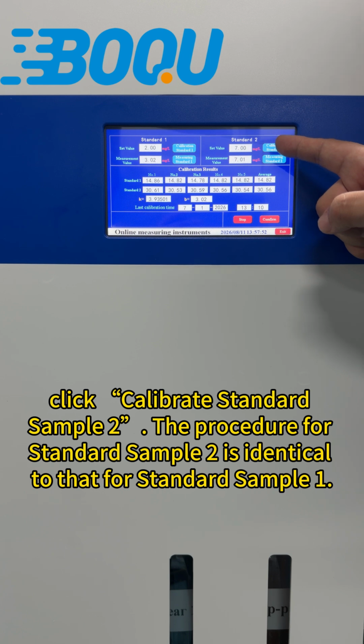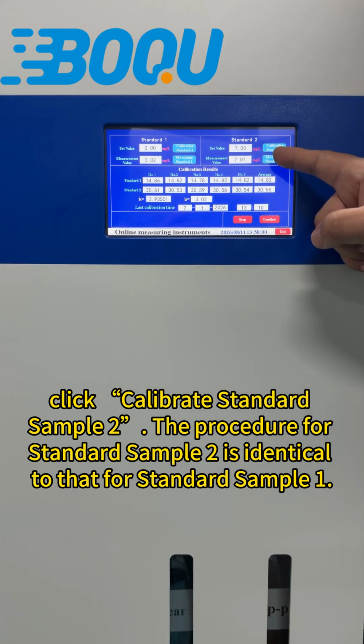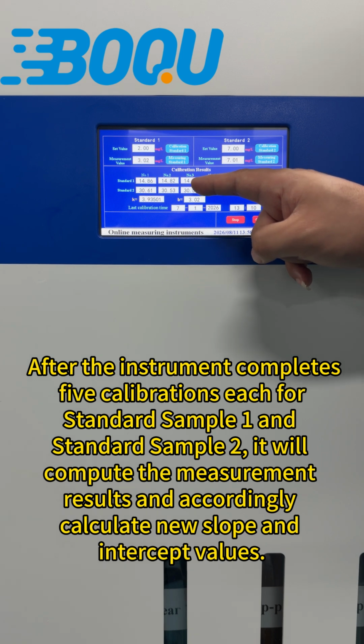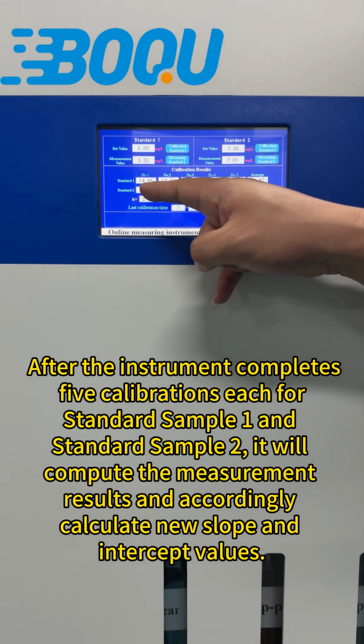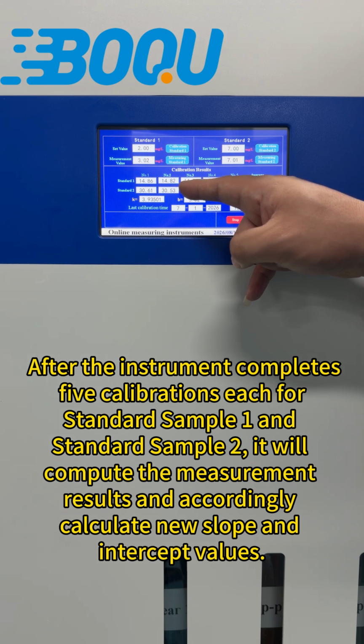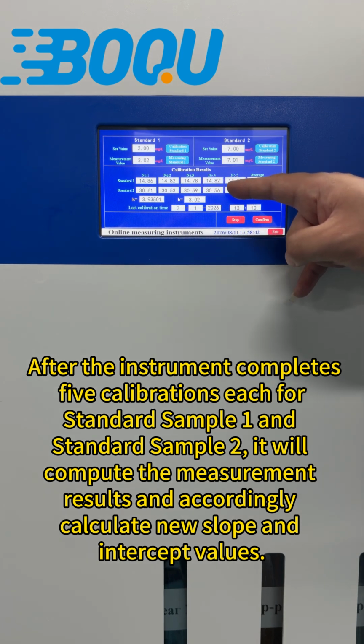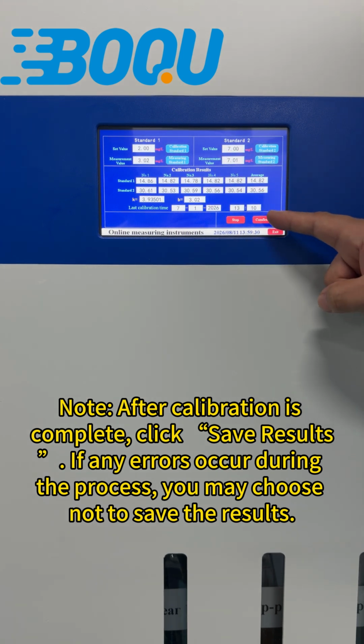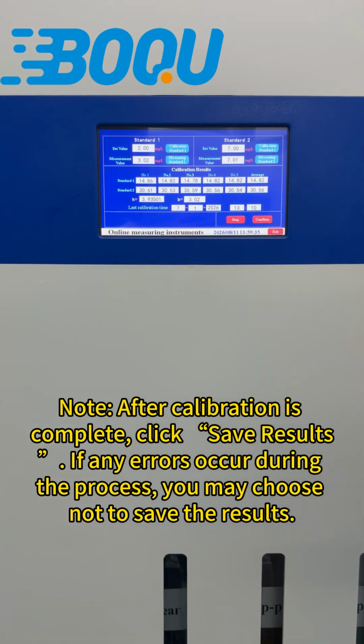Click Calibrate Standard Sample 2. The procedure for Standard Sample 2 is identical to that for Standard Sample 1. After the instrument completes 5 calibrations, each for Standard Sample 1 and Standard Sample 2, it will compute the measurement results and accordingly calculate new slope and intercept values. Note: after calibration is complete, click Save Results. If any errors occur during the process, you may choose not to save the results.